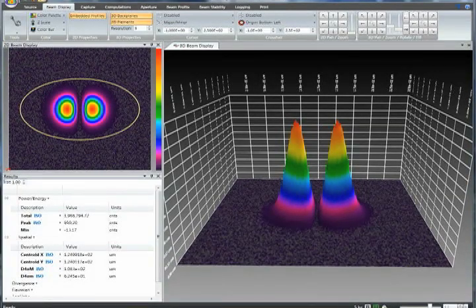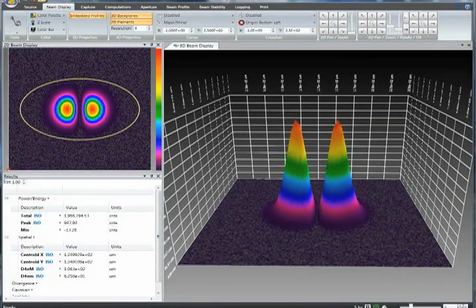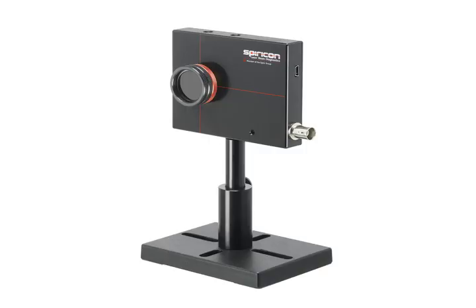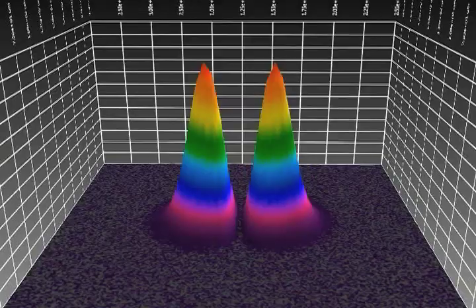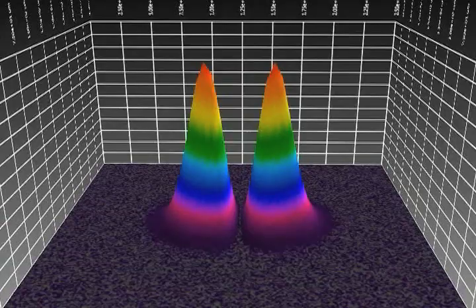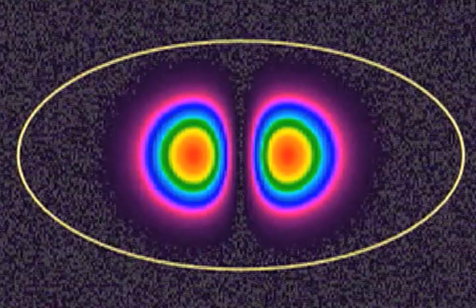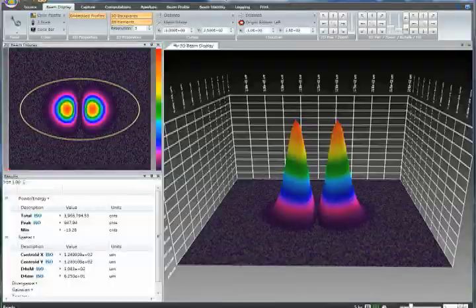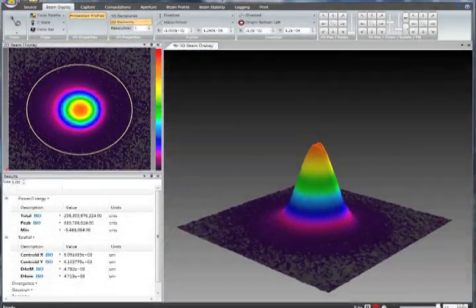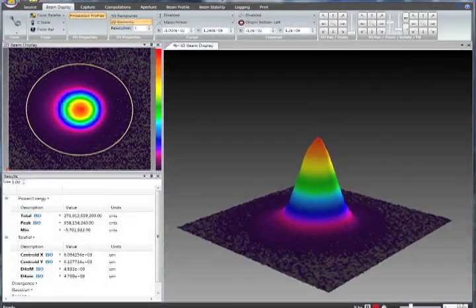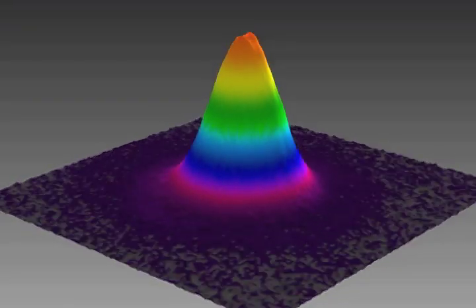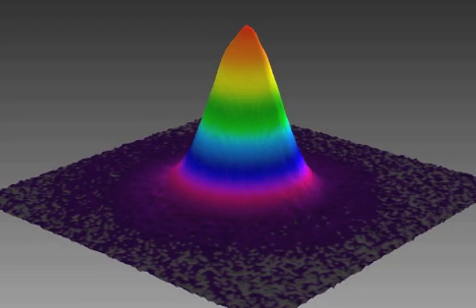This YAG laser beam was used to mark medical devices. The Spiricon beam profiling system displayed a deformed, two-peak beam, causing unreadable serial numbers. Adjusting the laser restored the beam to a Gaussian profile, properly focusing power and restoring quality to the process.